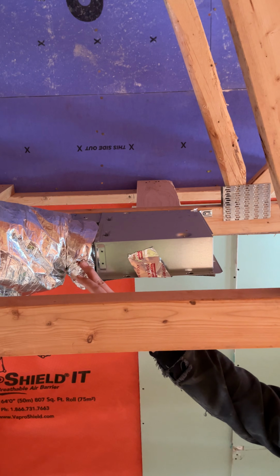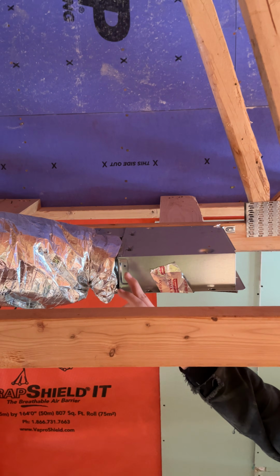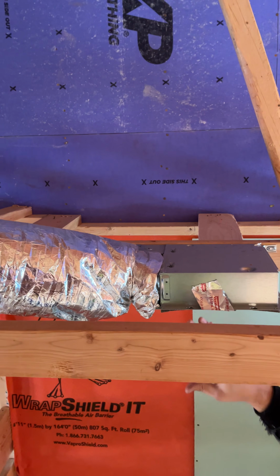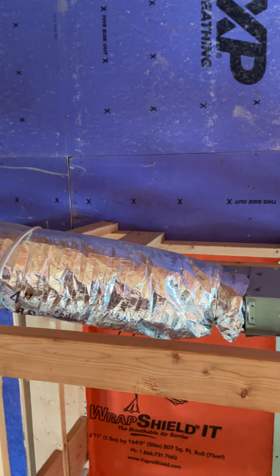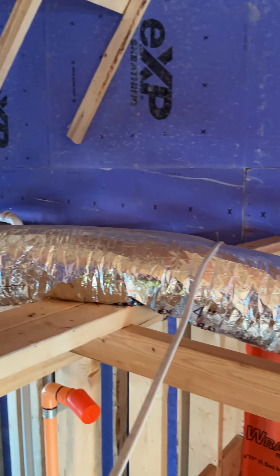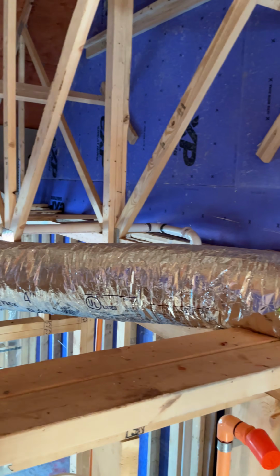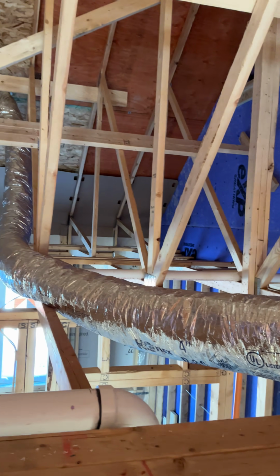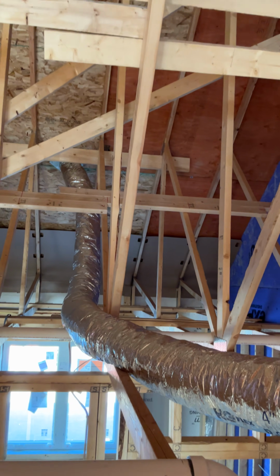So here we see a bathroom exhaust fan. One thing to point out is that you do not want to bunch up your duct insulation at the end here. That can cause the damper to block, but what we want to see is insulation covering the entire ductwork. We want a straight run with no dips or drops, nowhere that can collect water, and we want it fully insulated all the way out through the roof line.